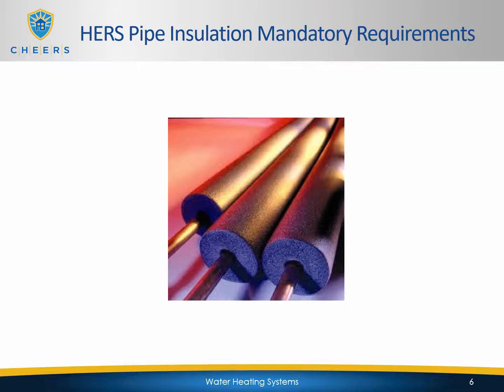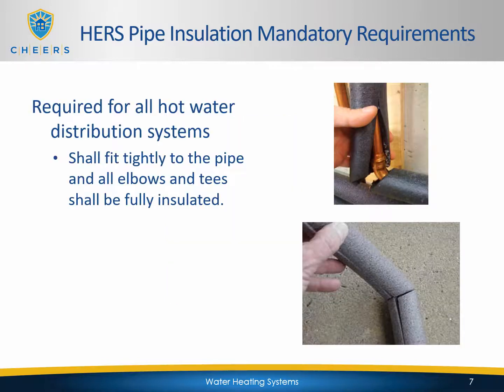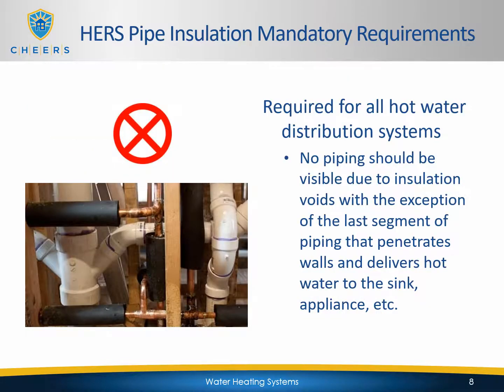So first we're going to be covering the HERS pipe insulation mandatory requirements. It's required for hot water distribution systems where the insulation shall fit tightly to the pipe and all elbows and tees shall be fully insulated, as shown in the pictures. No piping should be visible due to insulation voids, with the exception of the last segment of piping that penetrates walls and delivers hot water to the sink, appliances, etc.